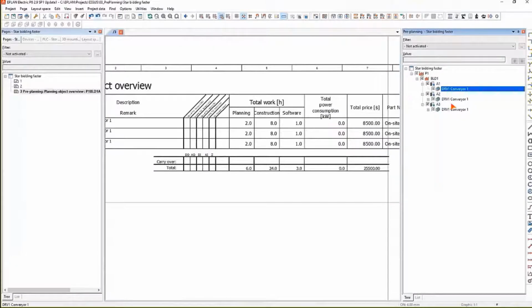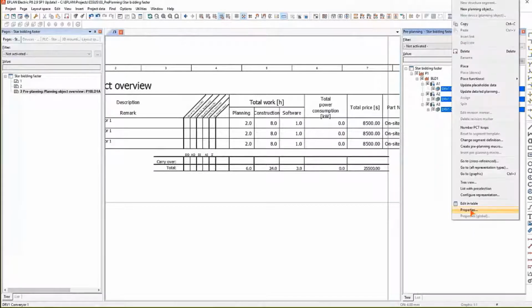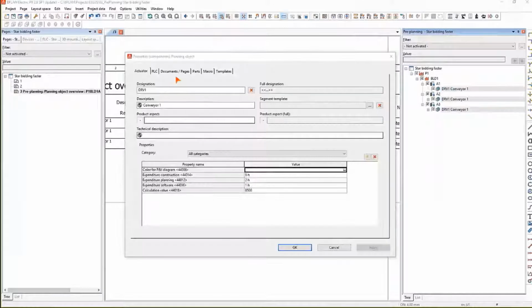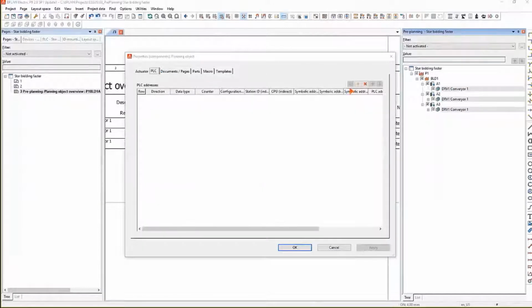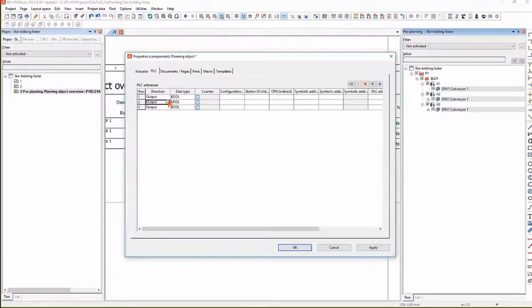So I'm going to select all these drives since they're very similar. I can add, for example, PLC I/O. I need an output to start the motor, so it's going to be a digital output. I'm going to start it with contactors, for example. Then I'm going to add 2 or 3 more inputs for motor start, motor stop, and motor fault.